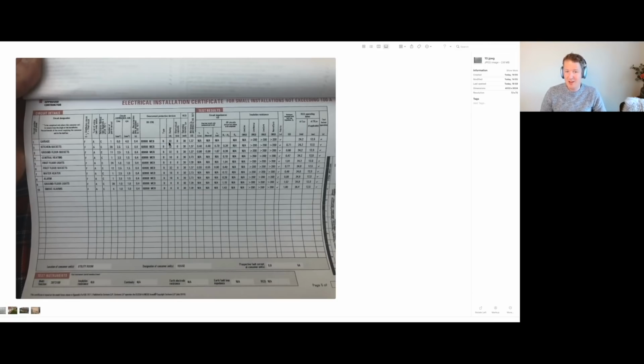Originally, though, it was on a 32 amp circuit breaker, so it seems like somebody's upgraded that to a 40, maybe because they were finding overload and they were tripping the circuit. So there's definitely no spare capacity on that cable for us to upgrade the circuit breaker. So back to square one now. We're going to have to run power from the house consumer unit or another source if possible.